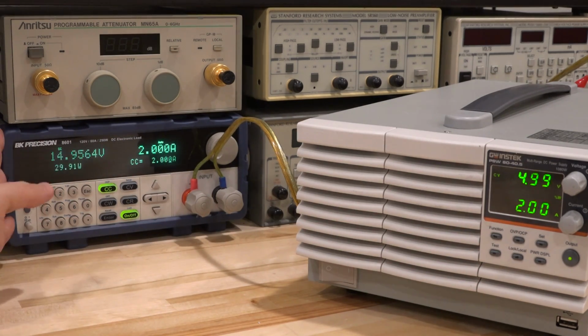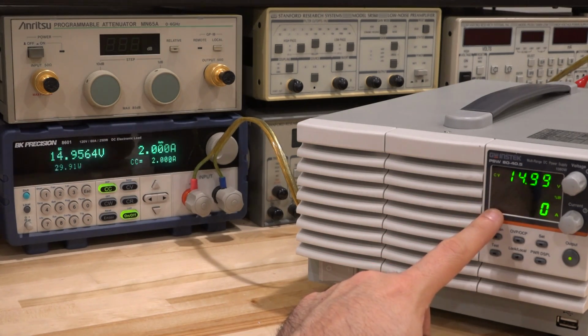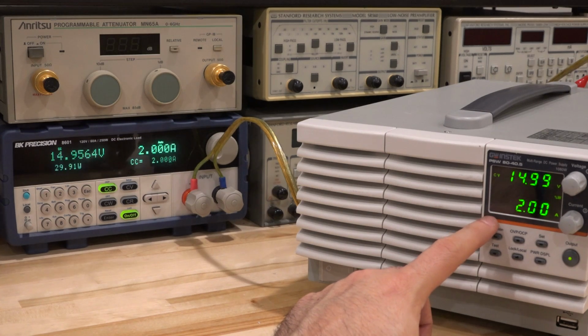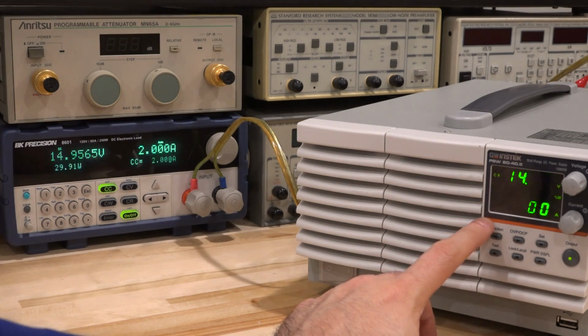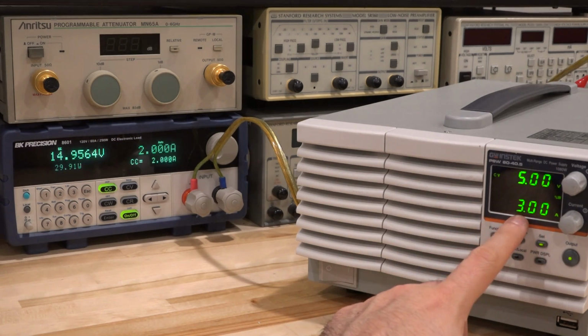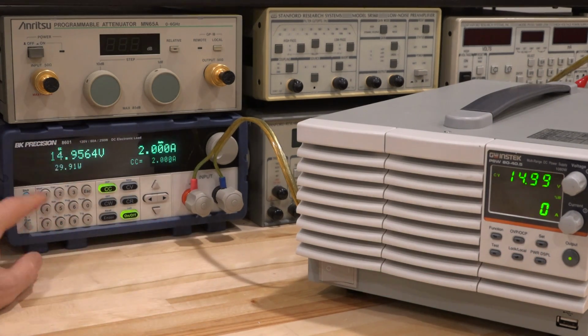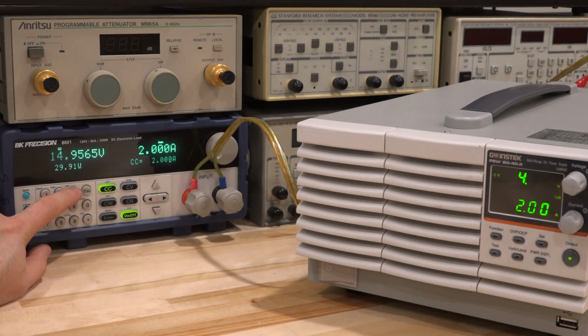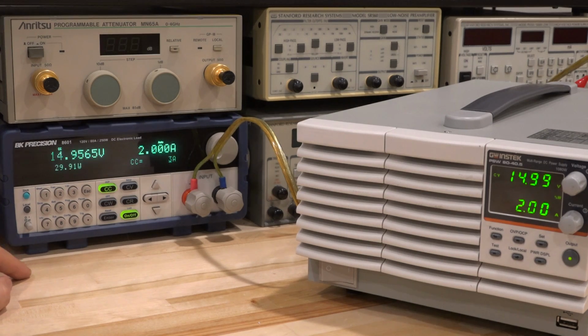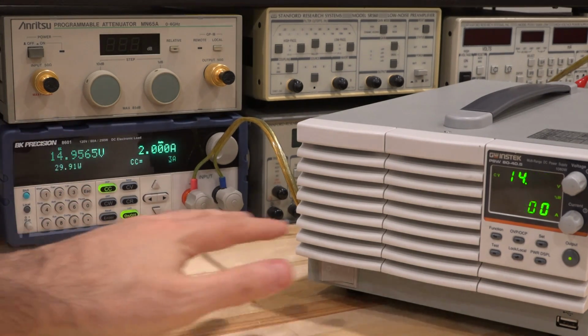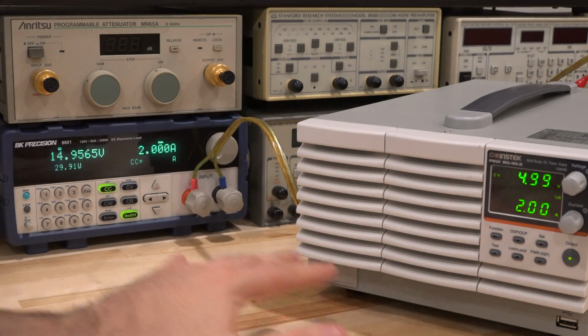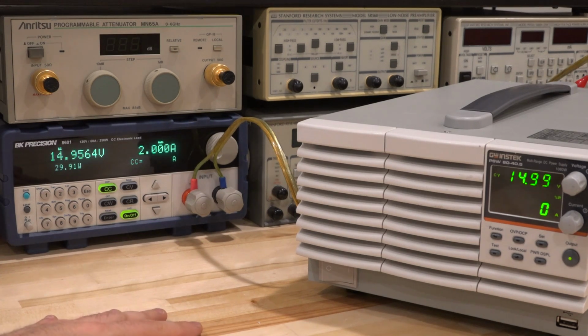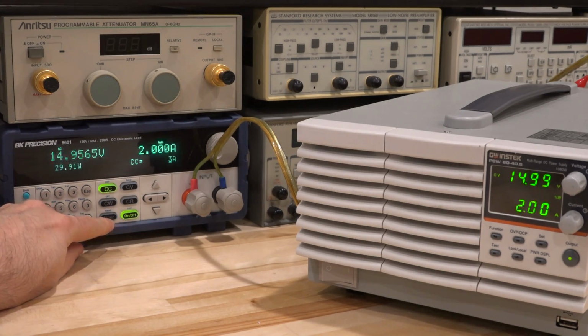Now at 2 amps, this is still in CV mode, constant voltage mode, hasn't gotten into constant current. I want to bring it into constant current. Now this limit is set to 3 amps. If I set this to 3 amps, I might get them into a runaway situation with respect to each other, because this will demand 3, right at the edge. The voltage may fall, this will still demand 3, and the voltage will continue to fall, and it may go down like a linear ramp and collapse. Let's see if that happens.